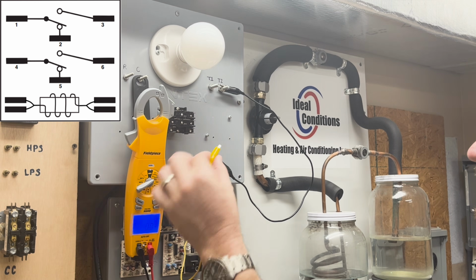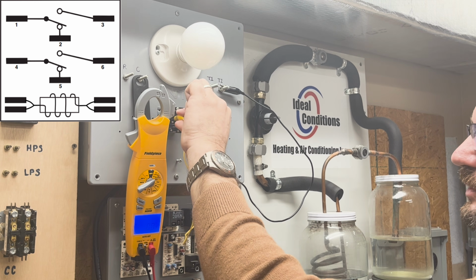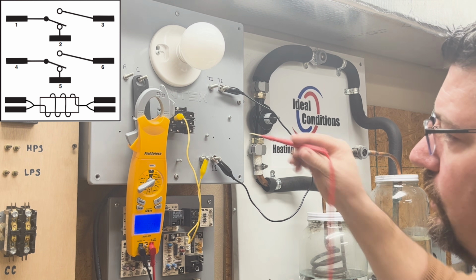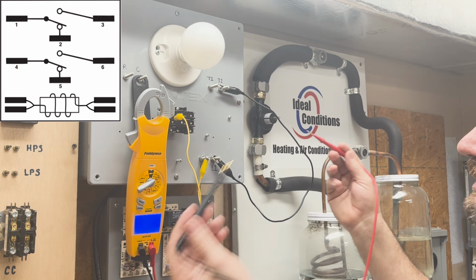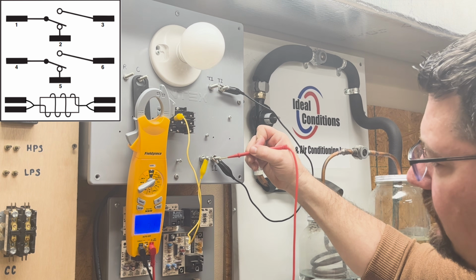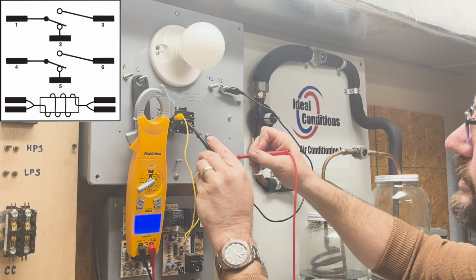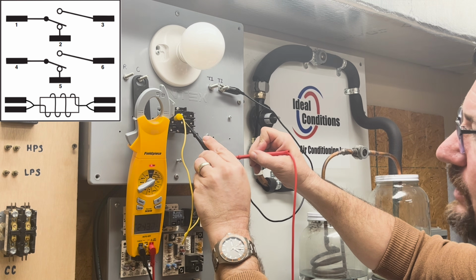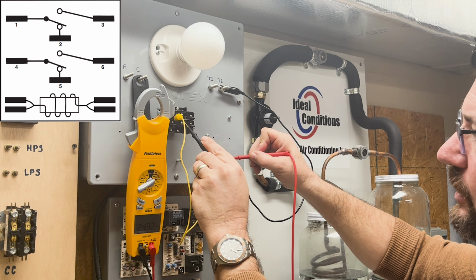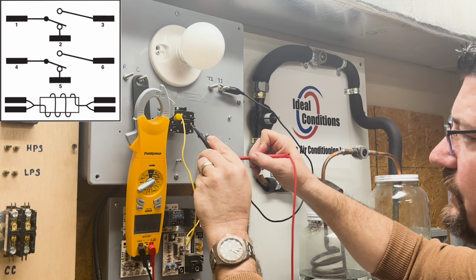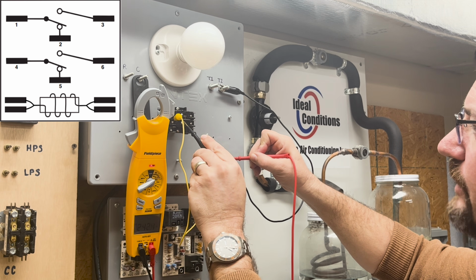So I'm going to come over here and I'm just going to shift this down to terminal 4, which is the second pole on this relay. And I'm going to have the exact same thing. I'll put one lead on L2. I'll put my other lead on terminal number 5, which is normally closed from 4. And as you can see here, I have 240 volts of power.